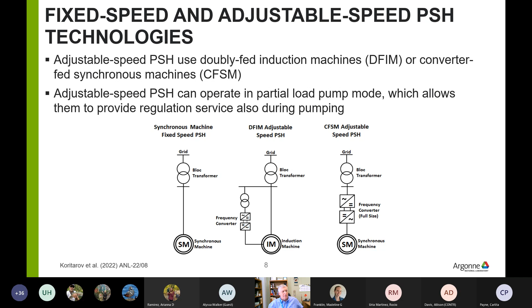they can provide more efficiency in the generating mode, but more importantly, they can pump with variable power consumption. Typically for pumping, an adjustable speed power plant can vary the power between 70% and 100% of the nominal power. That is very important for a number of reasons, and one is to provide more flexibility during the pumping, especially during the night hours when you need more flexibility, for example, to adjust the power output and compensate the variability of wind.